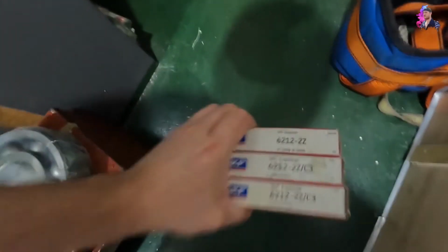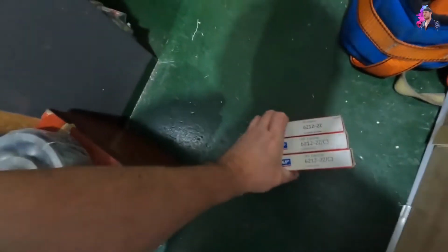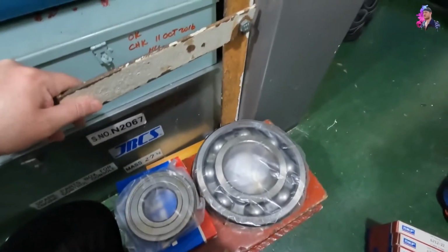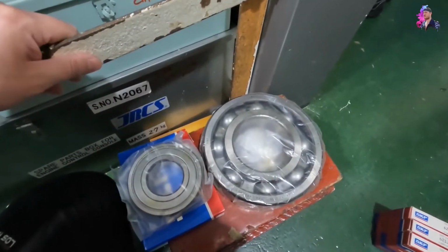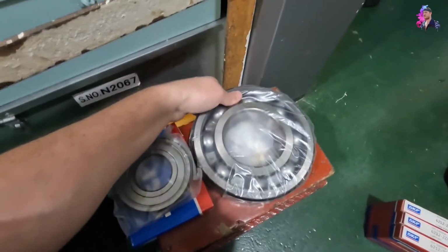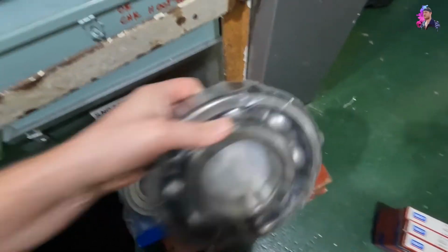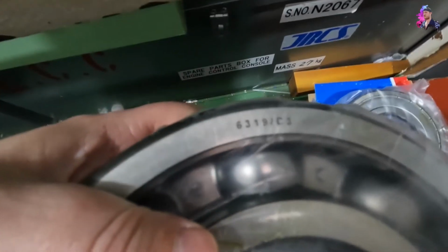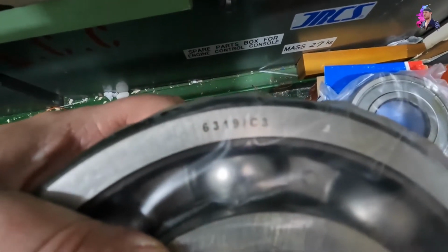And usually if you do not have the box of a bearing, or like I said, the motor that you want to change the bearing for is missing the nameplate, then when you open the motor you will see the code of the bearing written here. You see there, 6319.